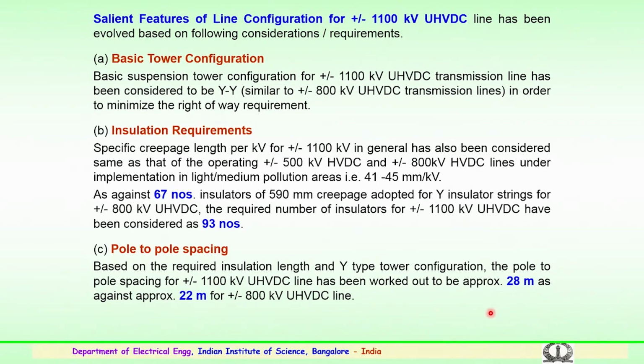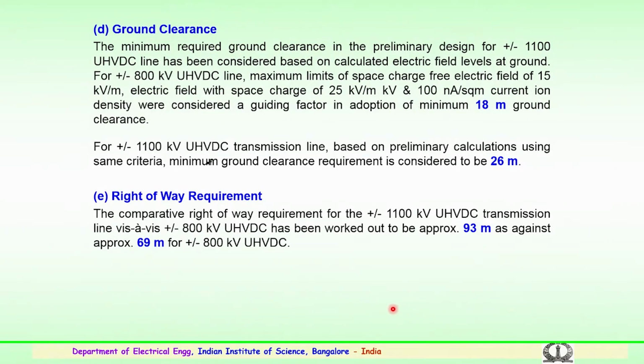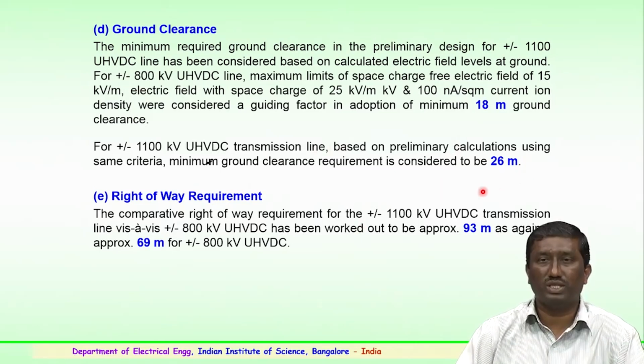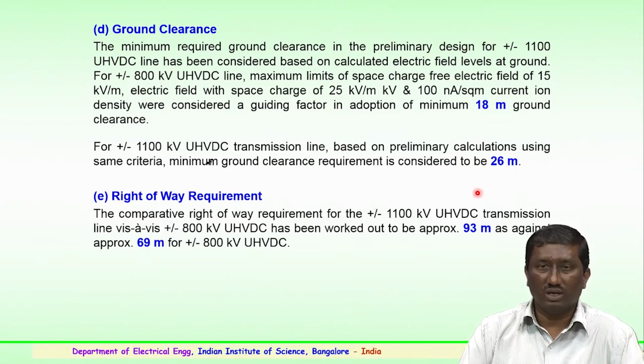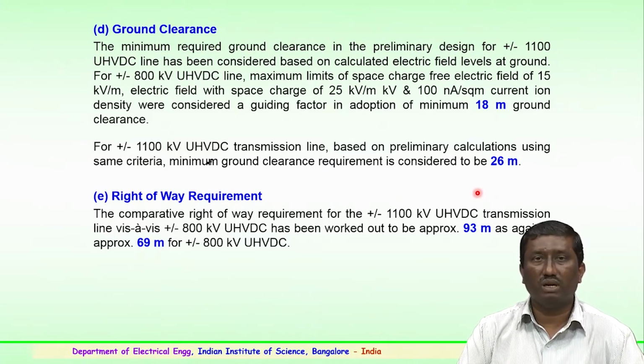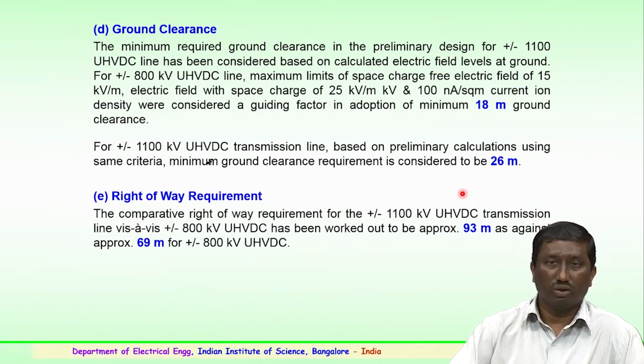So, maybe in a decade, a 1100 kV HVDC line could be transmitting much more power than the 6000 or 6500 megawatts which is being used by 800 kV. This will definitely be much more helpful for transmitting large chunks of power over long distances. So, what are the ground clearances in case of 800 kilovolts HVDC? We know that the minimum ground clearance is 18 meters and for 1100 kV it is estimated to be 26 meters. So, an increase of more than 8 meters from 800 kV DC to 1100 kV DC. So, a lot of activity is being done.